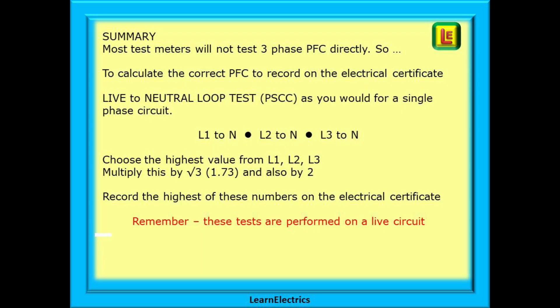A brief summary then. Most multifunction test meters will not test three-phase PFC directly. So, in order to calculate the correct PFC to record on the electrical certificate, we must carry out a live to neutral loop test, PSCC, just as you would for a single-phase circuit. We will do three tests and write down the results for comparison: L1 to neutral, L2 to neutral, and L3 to neutral. Then, we choose the highest value from the L1, L2, L3 tests. Multiply this highest value by root 3, or 1.73, and also multiply it by 2. Record the highest of these numbers on the electrical certificate, which is usually the times 2 value. And do remember, these tests are performed on a live circuit. Always work safely at all times.